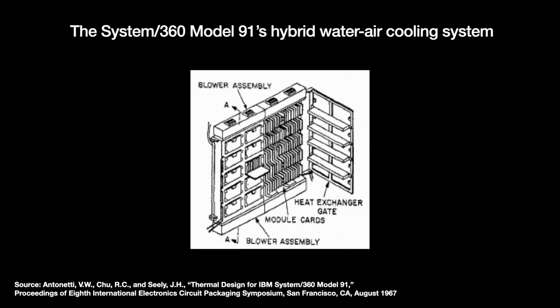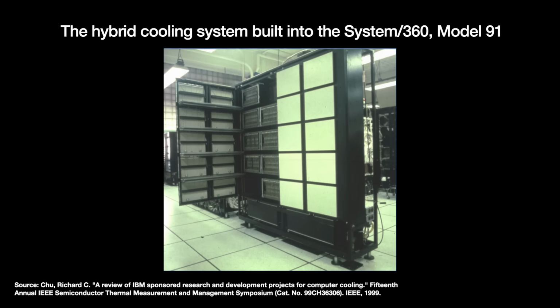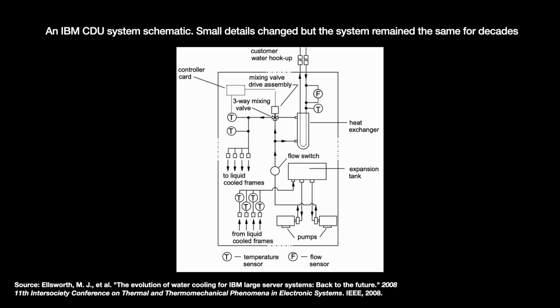Today, these arrangements are called hybrid or indirect liquid cooling systems. IBM people later recognized that the quality of the water mattered in cooling efficiency, and since customer water can be somewhat dodgy, they built a two-loop system. The inner loop is a closed one with purified water going to and from the circuits carrying heat, and then exchanges heat with the outer loop, which was filled with customer water.